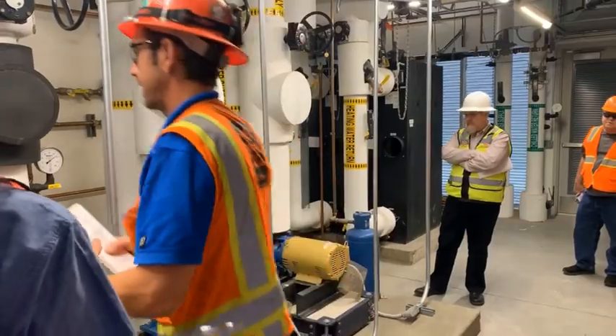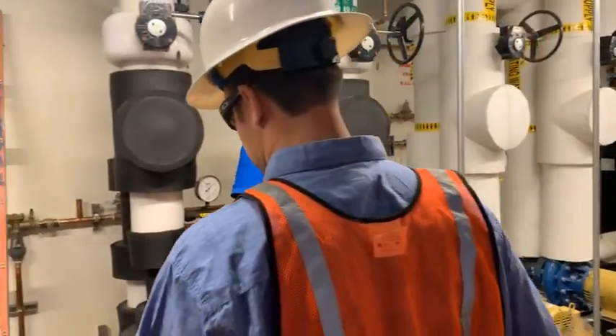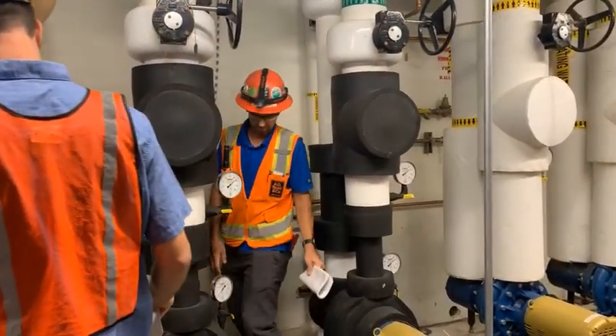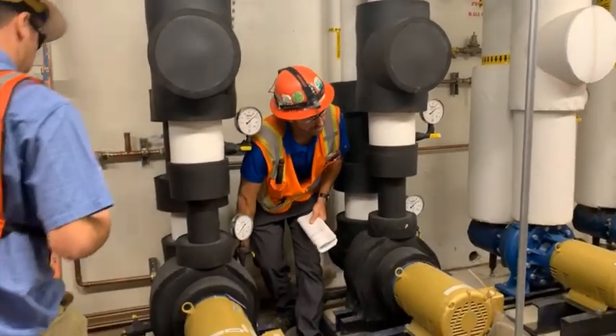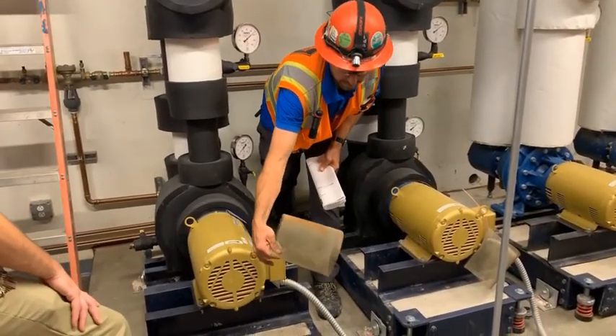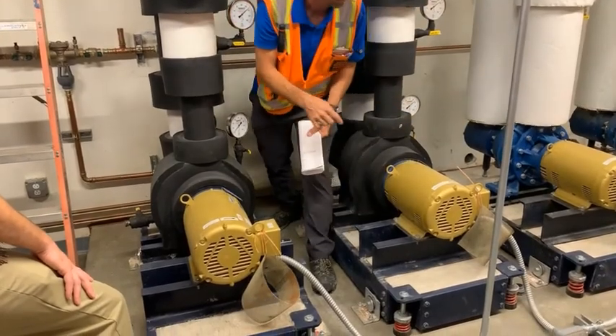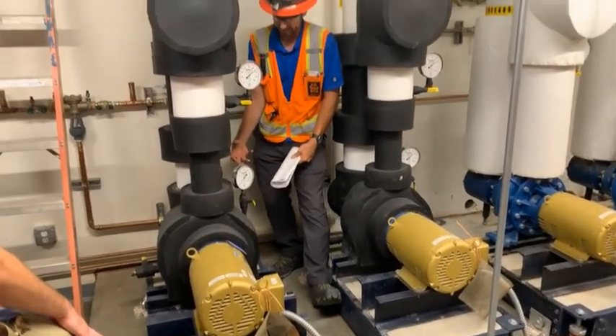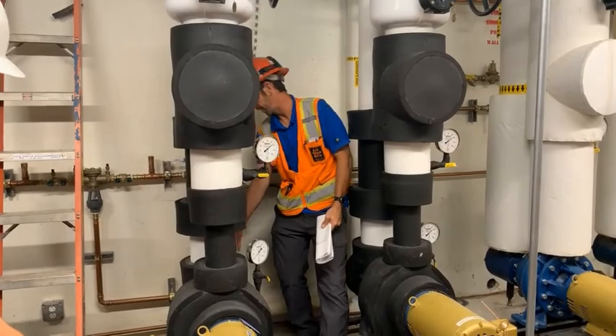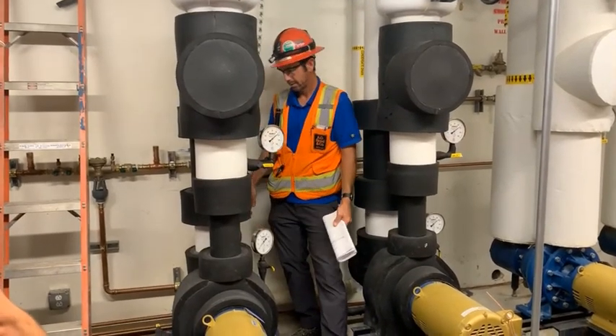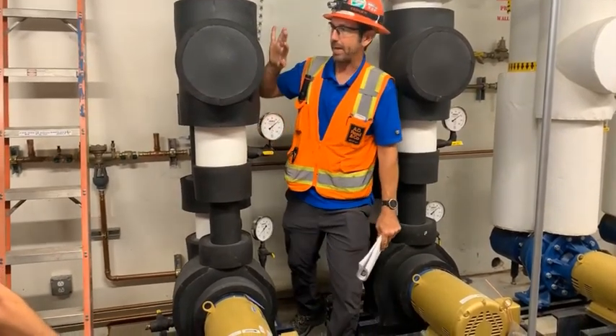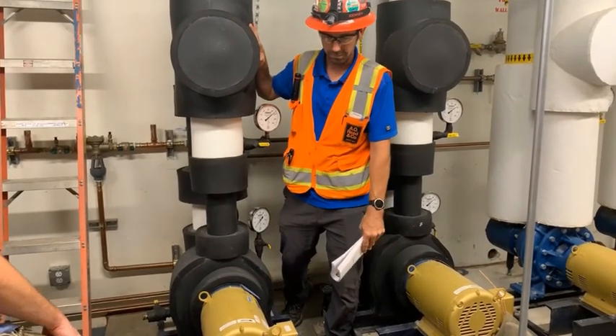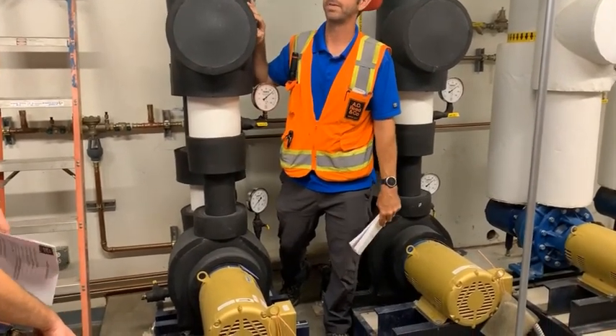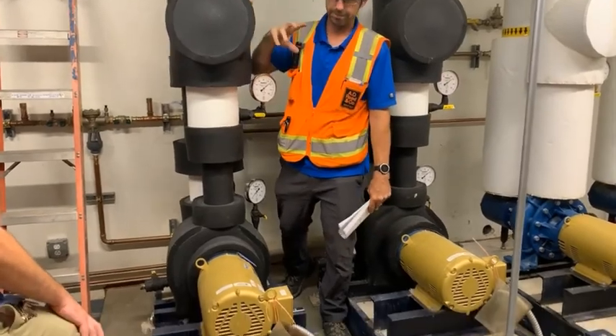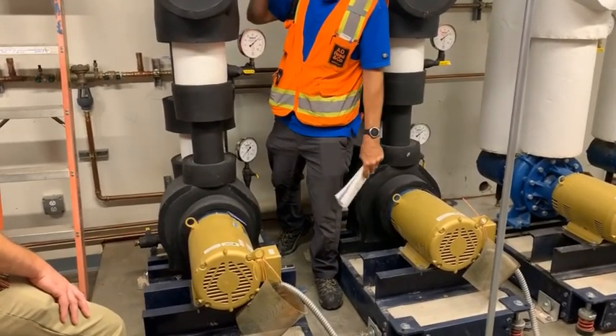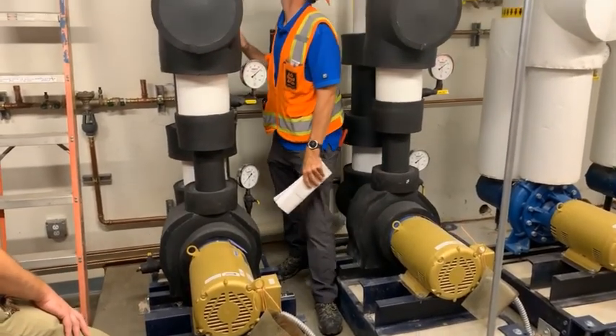Each pump has a suction diffuser. Does everybody know how a suction diffuser works? Yes. Okay. There is a screen inside. As you can see, I pulled the startup strainers out on all the pumps. Okay. The final screen is still installed. You'll get to that through the back end here. Every pump has a check valve too. The final screen is finer than that, or no, it's going to be not as fine, right? Yeah, that's just for startup to get all the fine particulars. I think it's roughly like 1/8 inch opening holes or so on that screen.